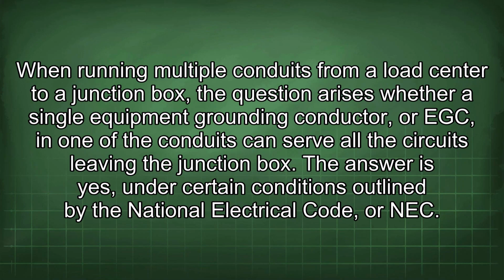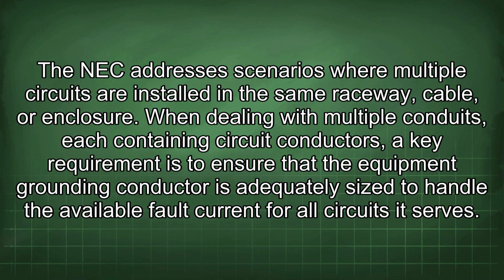When running multiple conduits from a load center to a junction box, the question arises whether a single equipment grounding conductor, or EGC, in one of the conduits can serve all the circuits leaving the junction box. The answer is yes, under certain conditions outlined by the National Electrical Code, or NEC. The NEC addresses scenarios where multiple circuits are installed in the same raceway, cable, or enclosure.